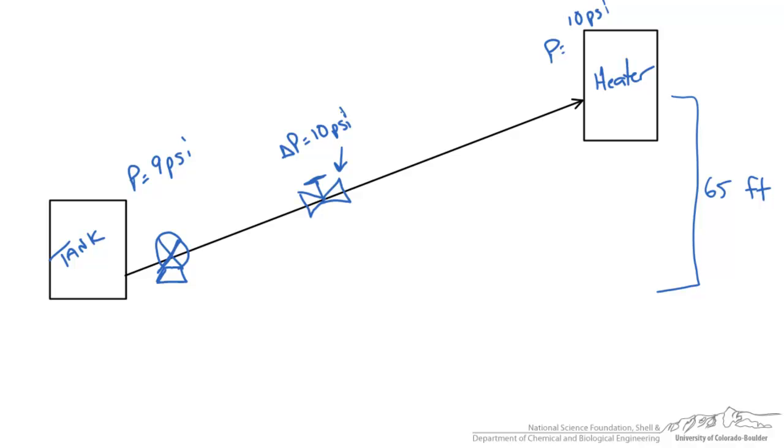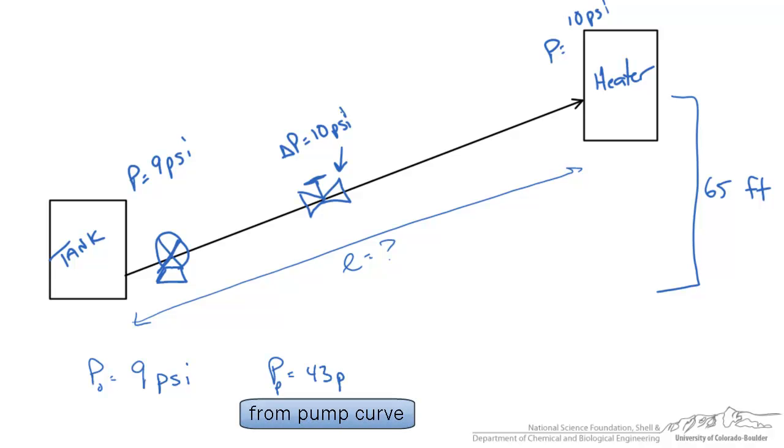At this point, we're going to do a pressure balance to determine the maximum length this pipe can be. We know our initial pressure is 9 psi, and to that we're going to add a pump pressure of 43 psi. That's our maximum head we can produce from the pump given the flow rate. Both of these pressures are positive because they're what we're starting with and what we're adding to the system.